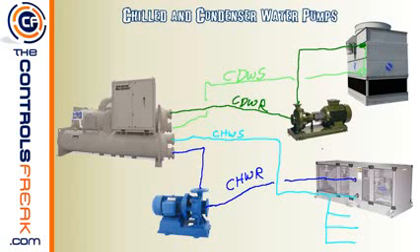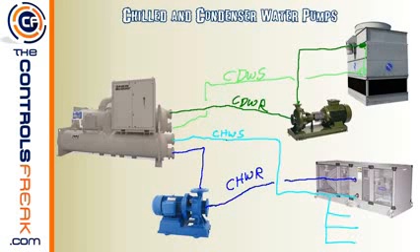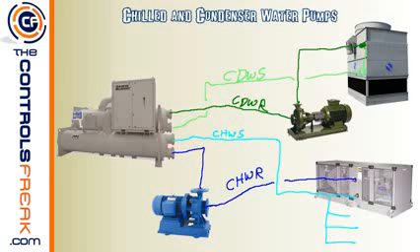A common question is how to tell the difference between supply and return. For chilled water, supply means you're providing chilled water — that comes from the chiller, so the water leaving the chiller is the chilled water supply. For condenser water, the cooling tower is what supplies the cold condenser water to the chiller, so that's the condenser water supply. The hot water leaving the chiller returns to the cooling tower, making it the condenser water return.